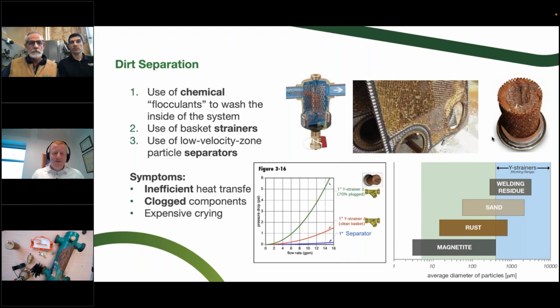But like Mack said, when you have a dirt separator, all that dirt and debris falls to the bottom of the cup in that basket, and it falls outside of the flow path, which means that you're not going to be interrupting any flow, causing any more unnecessary pressure drop. It's going to be great for your system. Not only that, like Mack said, it takes out smaller particles than what that strainer is capable of too. Which is all in all a good thing.